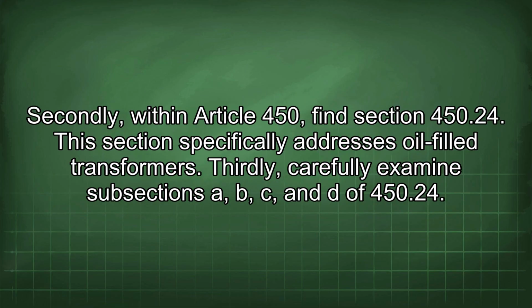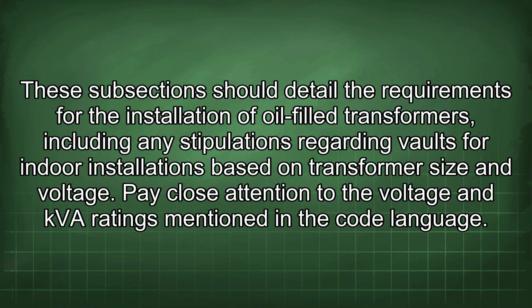Secondly, within Article 450, find Section 450.24. This section specifically addresses oil-filled transformers. Thirdly, carefully examine subsections A, B, C, and D of 450.24. These subsections should detail the requirements for the installation of oil-filled transformers, including any stipulations regarding vaults for indoor installations based on transformer size and voltage.